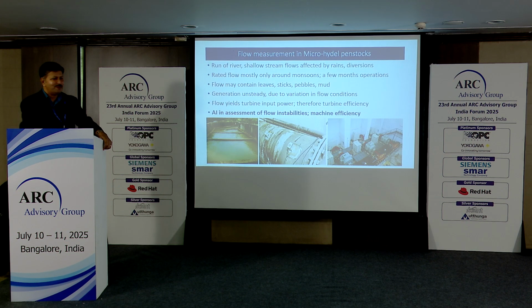Now coming to flow measurement in large diameter pipes, fundamentally we, as a testing agency, have worked on mini, micro and even large hydel projects. We have gone to sites for discharge measurement, for validation, and for what is known as field efficiency testing, where the turbine efficiency is determined at the time of installation and at commissioning, within 6 months of commissioning. Typically, for large diameter pipes, the most common flow meters are clamp-on type, but in certain cases the penstocks, or the pipes leading to your hydro turbines, may not have access where you can install any kind of flow meter.